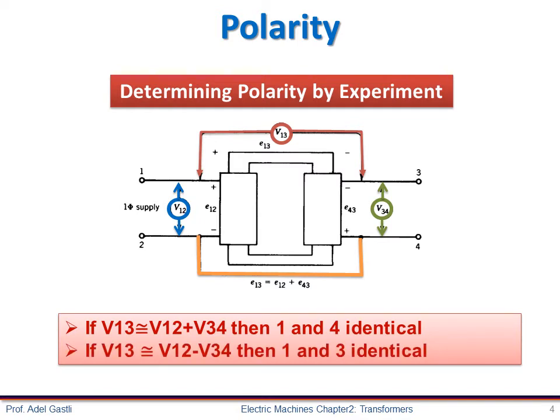But if V13 equals V12 minus V34, then terminals 1 and 3 have identical polarity. According to the connection and polarity of the transformer given in this example shown on this slide, voltmeter V13 will show the summation of primary and secondary voltages V12 and V34. This is called an additive condition.